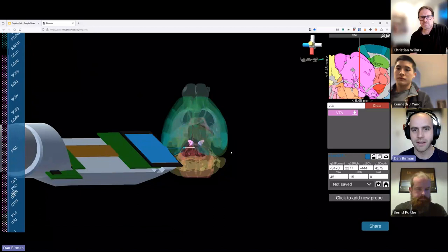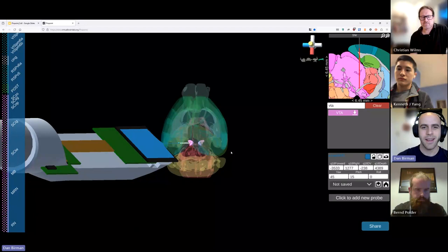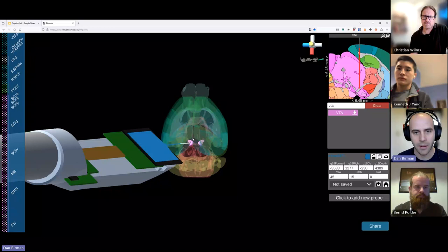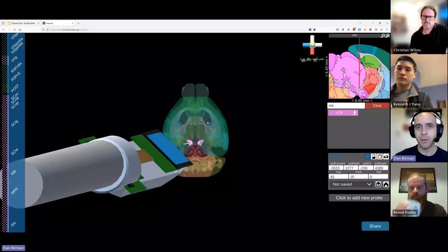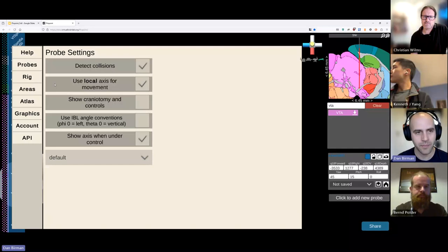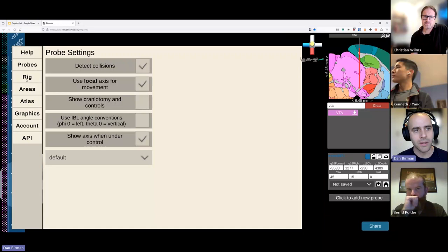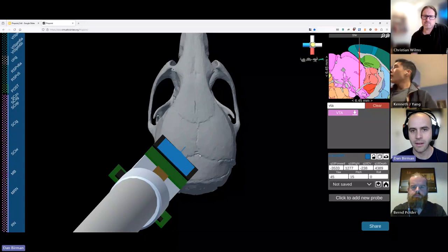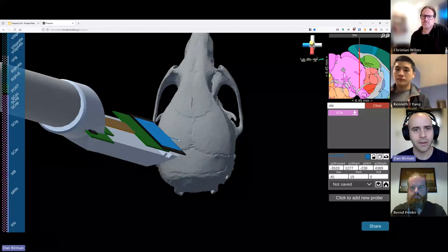The reason you might want to use local axis mode is that those are actually the X, Y, and Z axes of the manipulator — for example, a Sensapex manipulator. All the movements and coordinates on the right side are all relative to Bregma. Maybe you want to see where Bregma actually is on the mouse brain. You can go into the Help menu — accessed by pressing Escape — and under the Rig tab, you can turn on the Mouse Skull to see where the brain is relative to Bregma and Lambda.